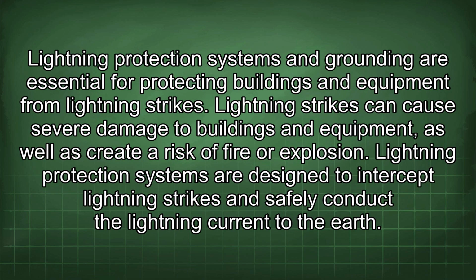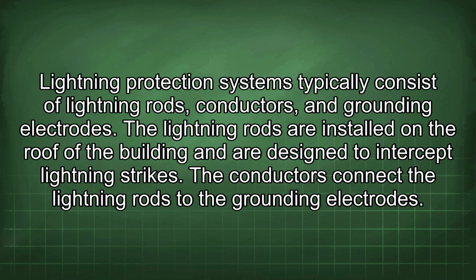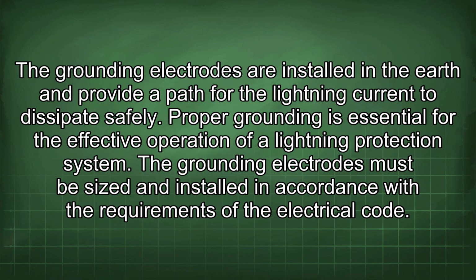Lightning protection systems and grounding are essential for protecting buildings and equipment from lightning strikes. Lightning strikes can cause severe damage to buildings and equipment, as well as create a risk of fire or explosion. Lightning protection systems are designed to intercept lightning strikes and safely conduct the lightning current to the earth. Lightning protection systems typically consist of lightning rods, conductors, and grounding electrodes. The lightning rods are installed on the roof of the building and are designed to intercept lightning strikes. The conductors connect the lightning rods to the grounding electrodes. The grounding electrodes are installed in the earth and provide a path for the lightning current to dissipate safely. Proper grounding is essential for the effective operation of a lightning protection system. The grounding electrodes must be sized and installed in accordance with the requirements of the electrical code.